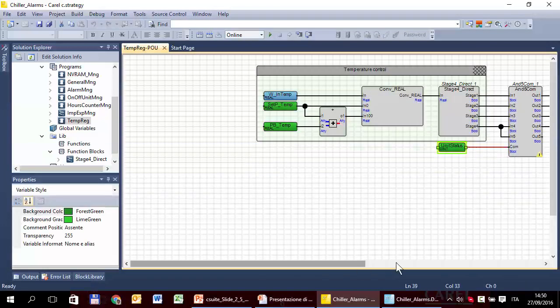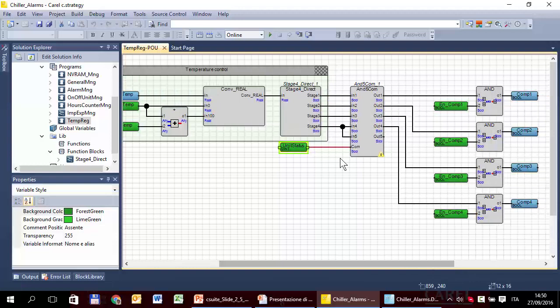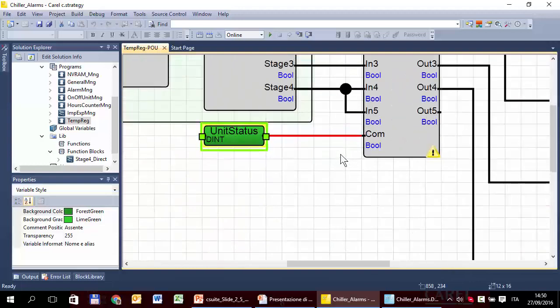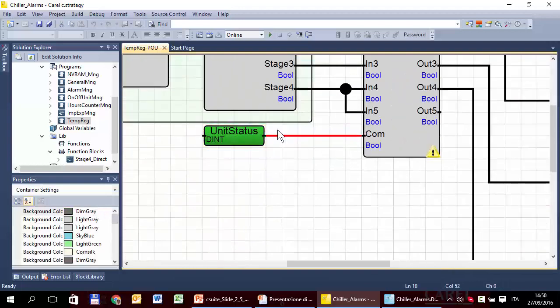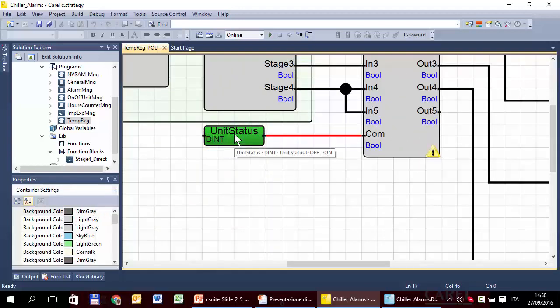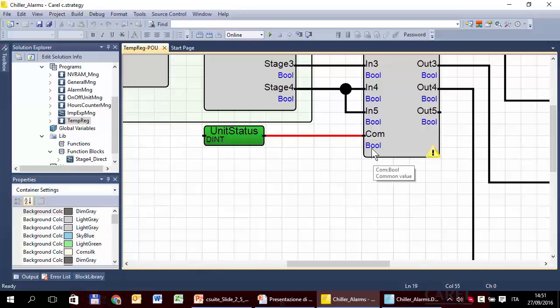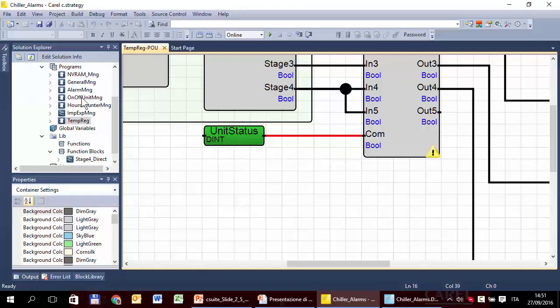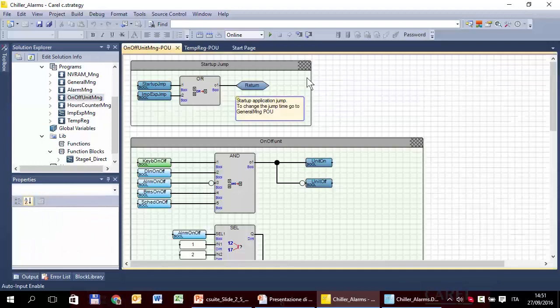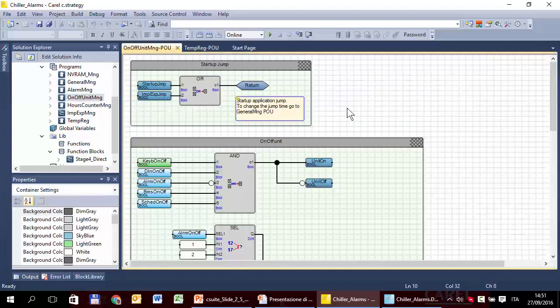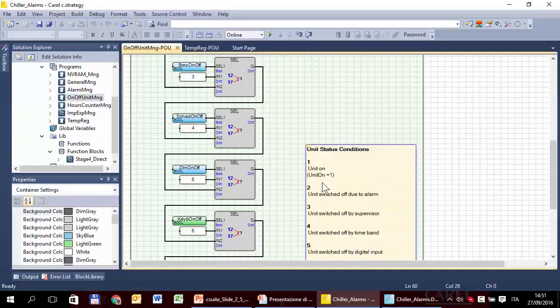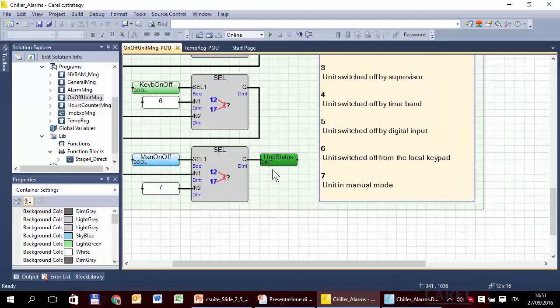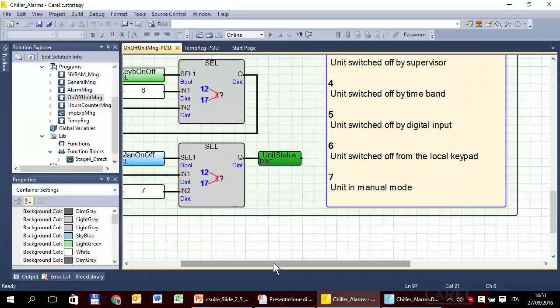What's wrong with this strategy? It worked before in the chiller project. The problem is that this UnitStatus is a double integer data type, while this block requires a boolean. But why before worked and now doesn't work? Because UnitStatus is a double integer and it is used... We could use the find, but I already know that it is here.